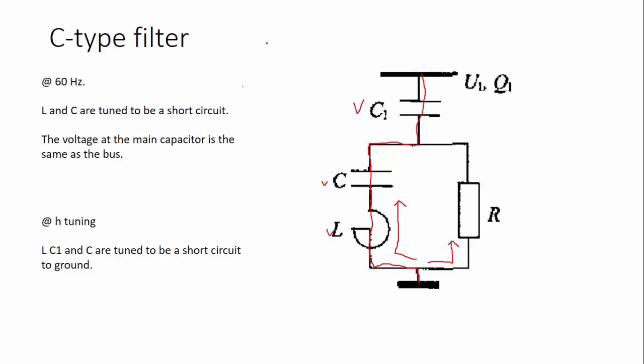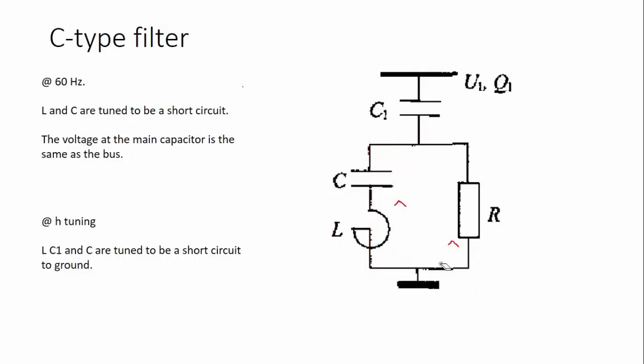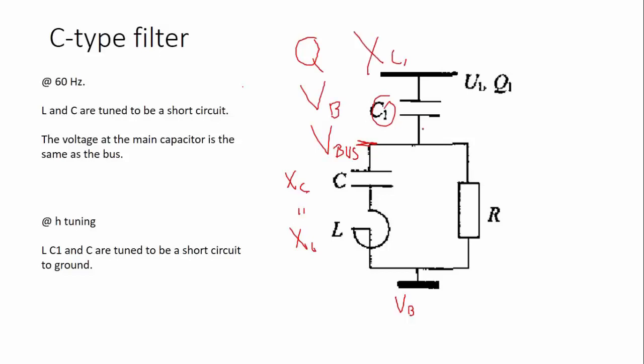So I'm not going to bore you with algebra. It has a lot of algebra implied, and it's not hard, but I don't think that's the point of the webinar. So as you might see, at 60 Hertz, we want this reactance and this reactance to be equal. So this is a short circuit, and then we have only this. The bus voltage, since this is a short circuit, will appear in here. So it's very easy to estimate this capacitance if we know how much power we want to draw from the filter and the bus voltage. So XC1 is fairly easy to estimate along with C1.